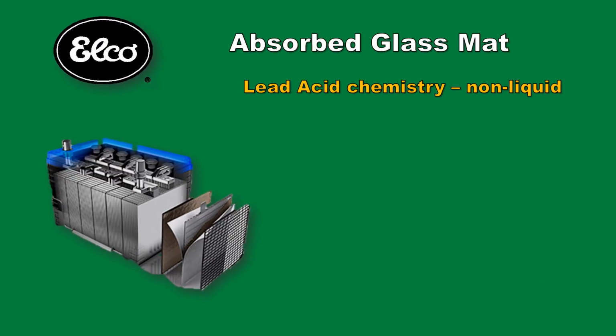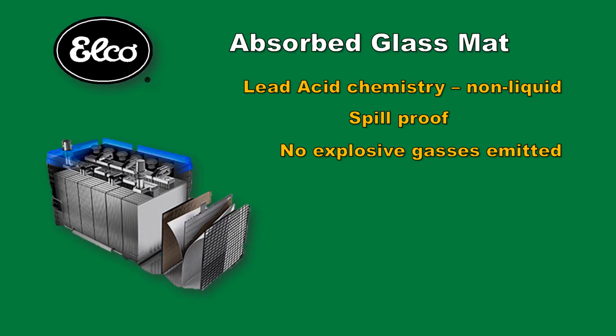AGM batteries are a lead-acid technology without the liquid found in flooded wet cell batteries. This has several advantages over the traditional flooded wet cells, which are not recommended by Elco. AGMs are spill-proof, meaning that the electrolyte is absorbed in fiberglass mats sandwiched between the battery plates, so there is no danger of spilling acid, even if the battery is punctured. AGMs do not emit explosive gases in any appreciable amount.